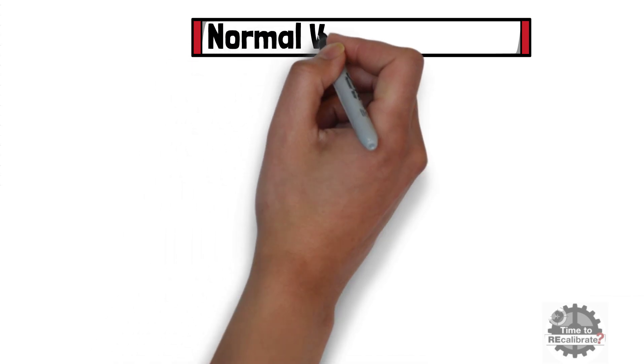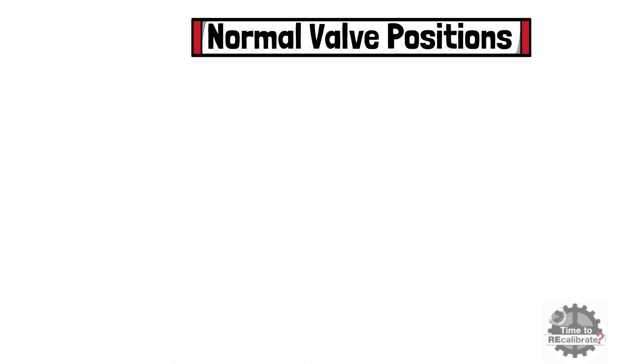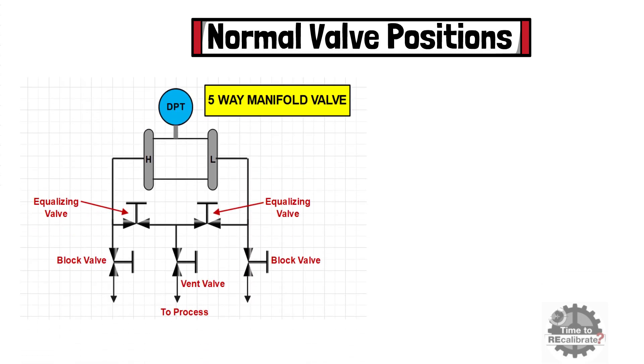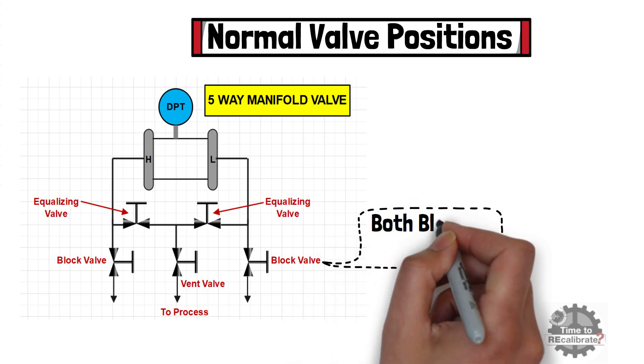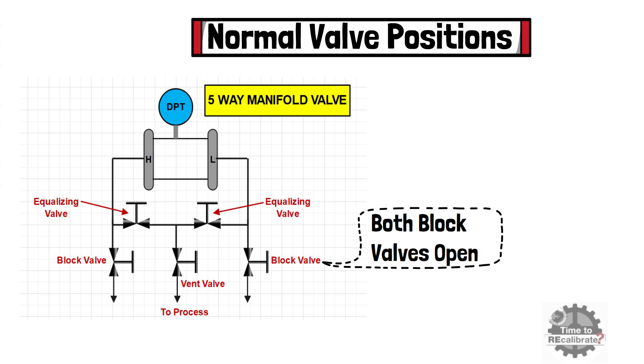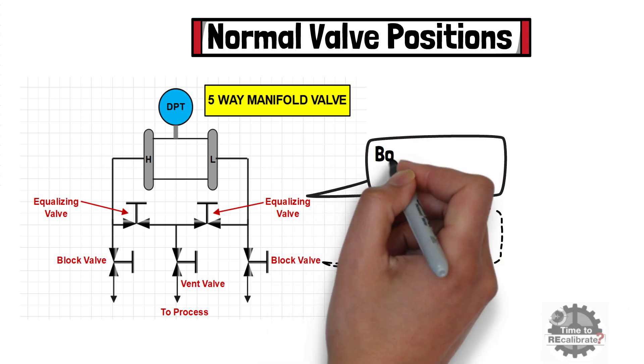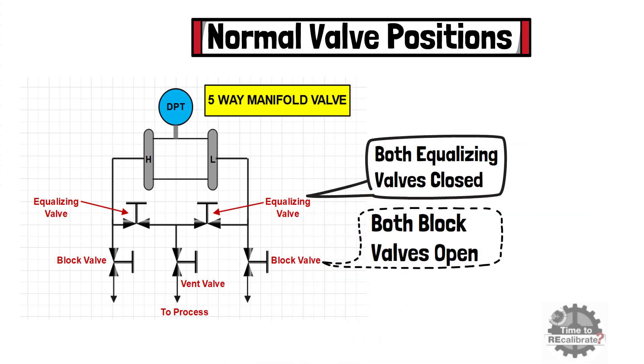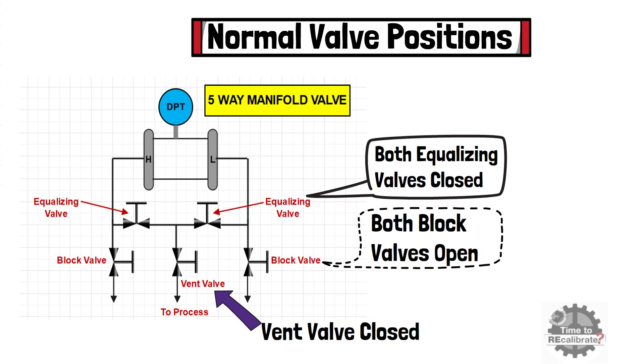First of all, let's learn what the normal valve positions of a 5-way manifold valve are when the differential pressure transmitter is in service. When the differential pressure transmitter is in service, both block valves will remain open, both equalizing valves will remain closed, and the vent valve will also remain closed.